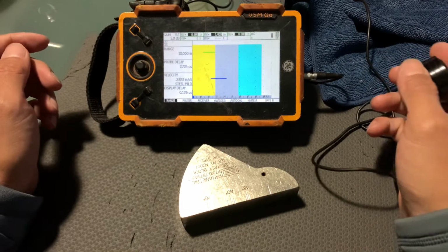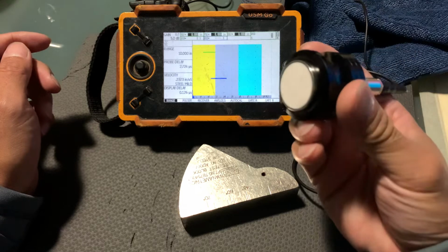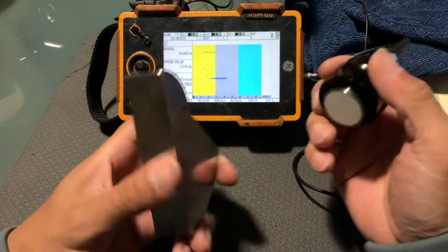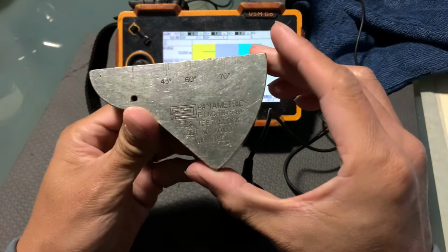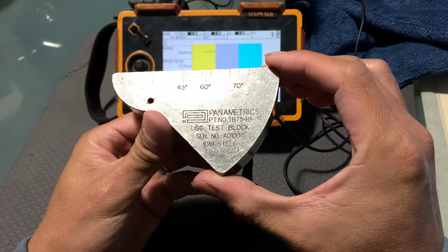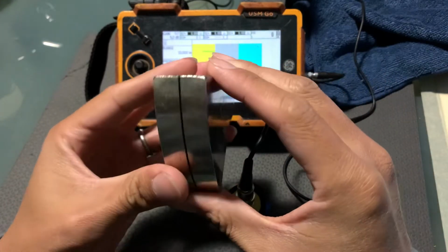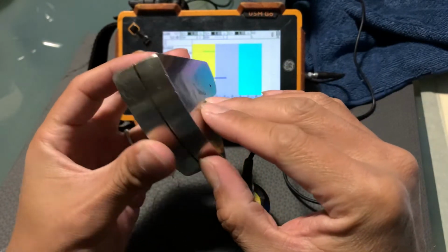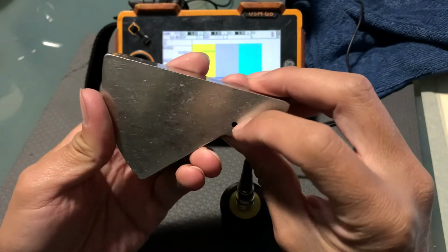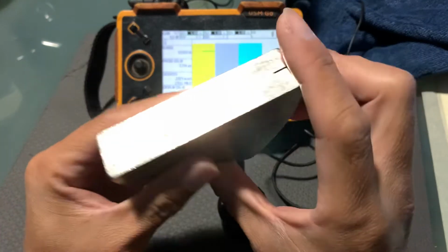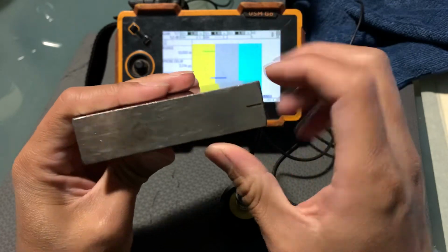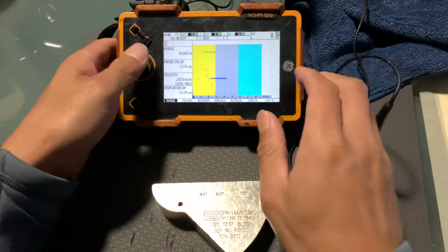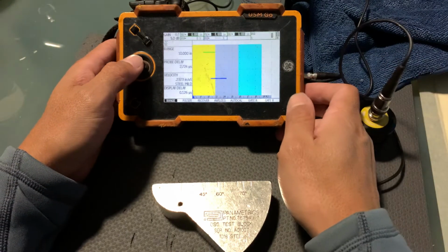Okay, today I'm going to show you how to calibrate your machine for a straight beam transducer. And we'll be using a DSC block. Notice you got a groove on this side, drill hole on this side. Standard DSC block, always 1 inch in diameter. So we're going to go through machine calibrations.